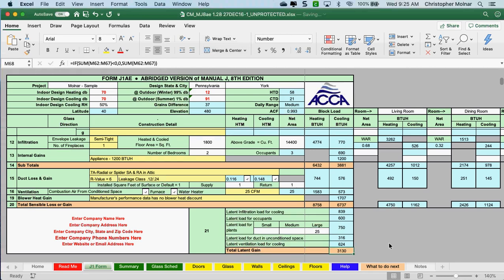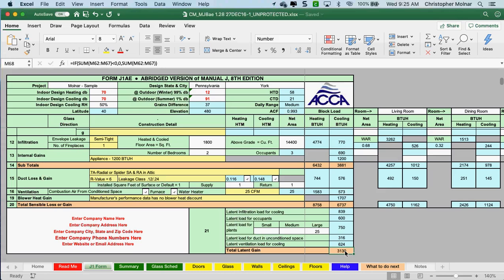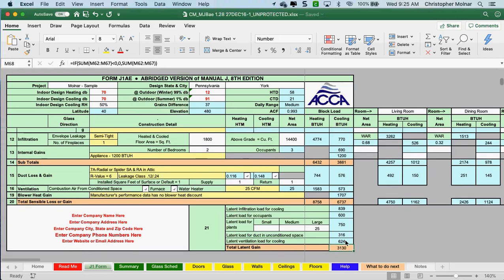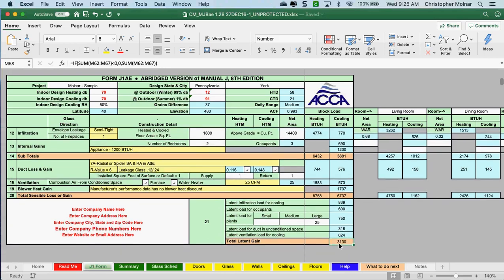Everything else comes in and once you have this filled out, you're down to your total latent gain. This is my sensible gain and this is my latent gain. Why does this matter? I really care about these two numbers because of equipment selection — my air conditioning unit has to be able to both remove the sensible heat and also deal with the latent heat.